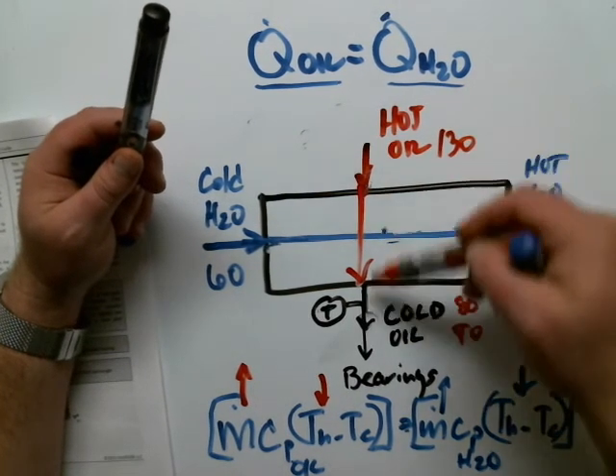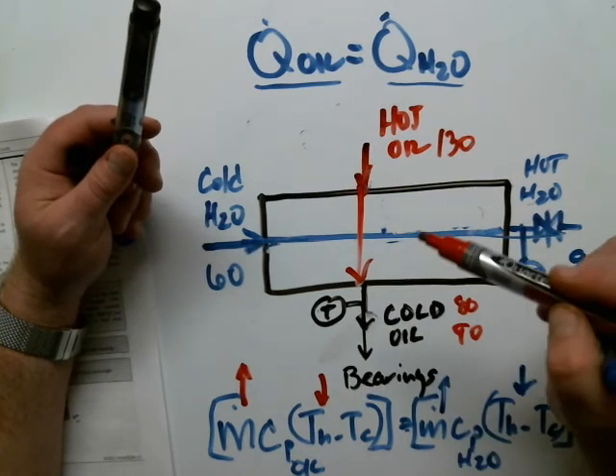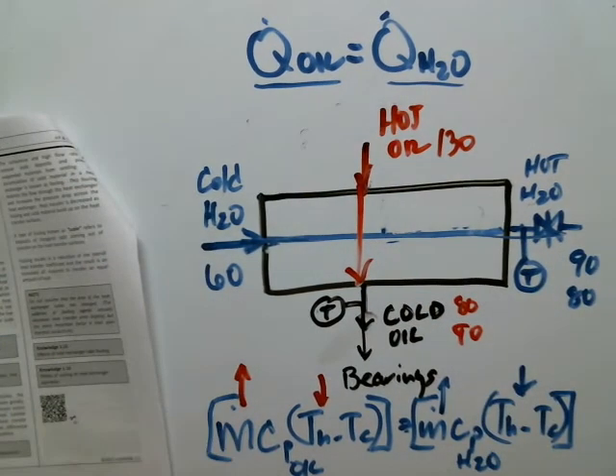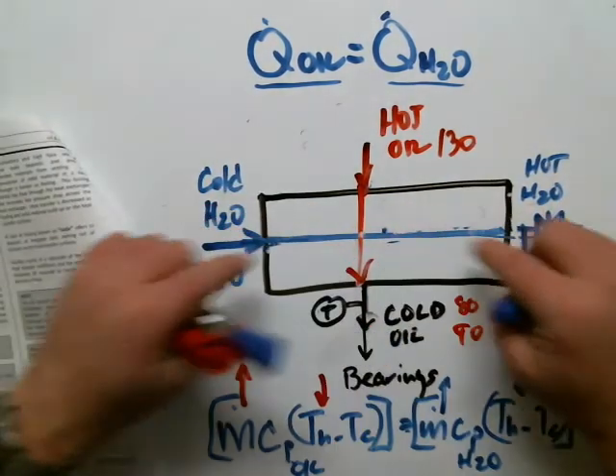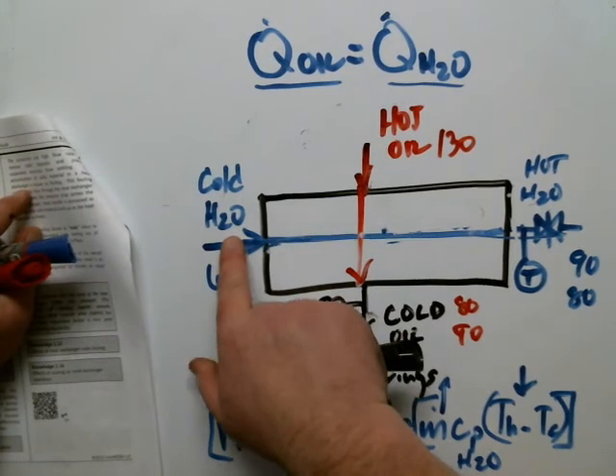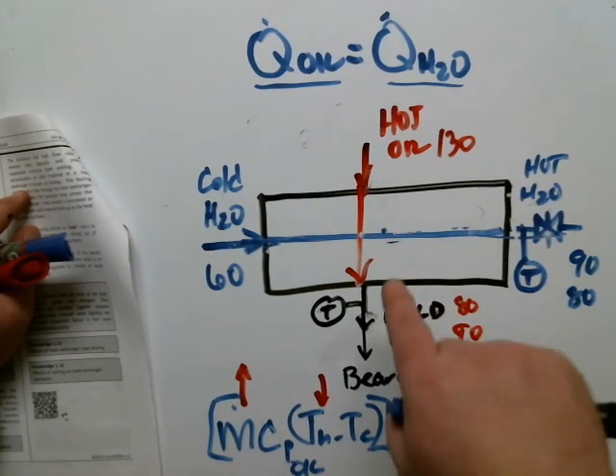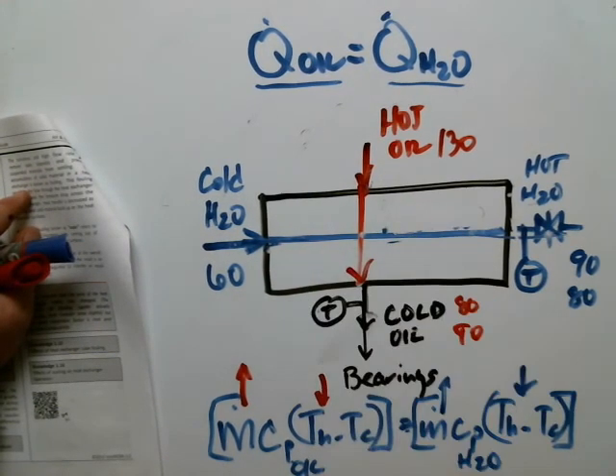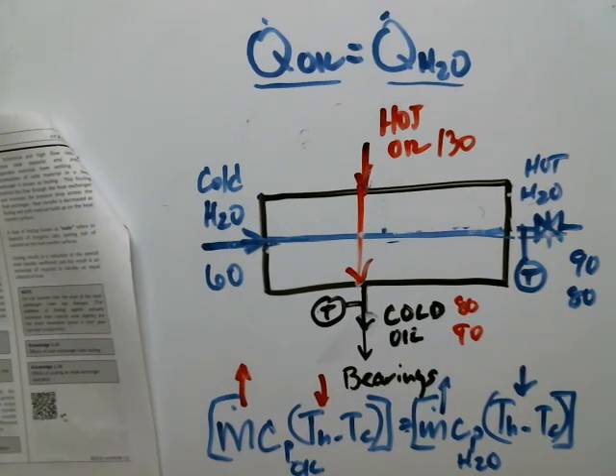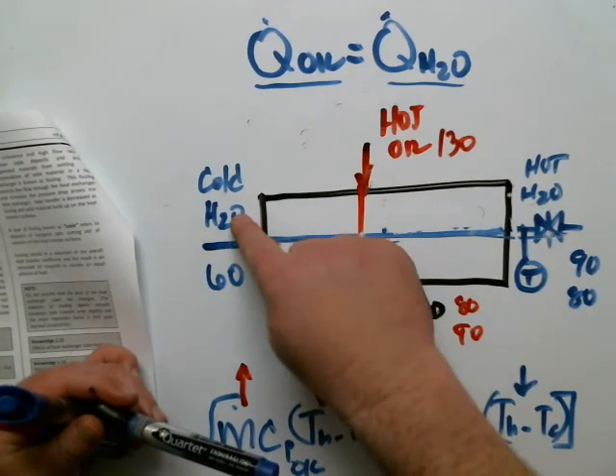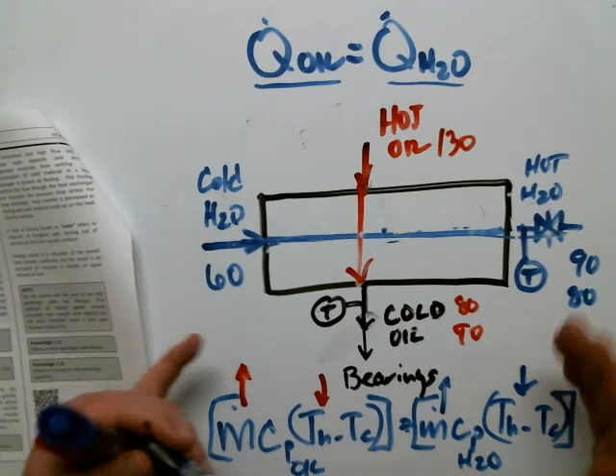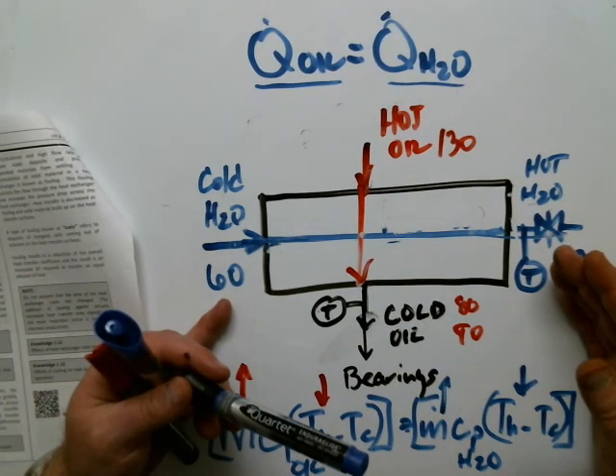Because we're putting more heat load on that water by putting more mass flow rate to it. So that's important to understand. And if fouling occurs, that's going to inhibit heat transfer. So the cold water will stay cold and the hot oil will stay hot. Because if you do anything to inhibit heat transfer, either via scaling or some sort of tube fouling, we're not going to get as much of the energy transferred from the hot fluid to the cold fluid. That's going to change differential temperatures for the given mass flow rates.